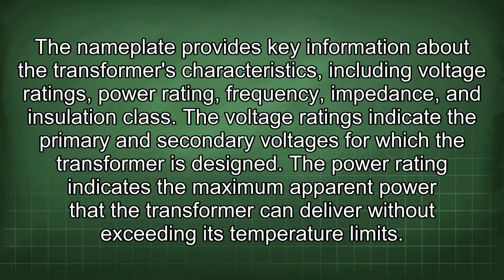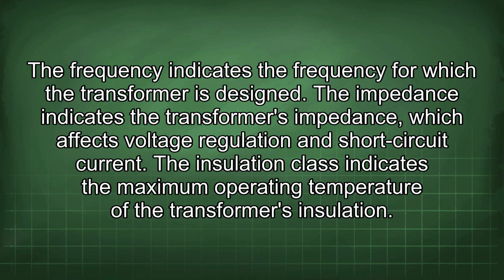The power rating indicates the maximum apparent power that the transformer can deliver without exceeding its temperature limits. The frequency indicates the frequency for which the transformer is designed. The impedance indicates the transformer's impedance, which affects voltage regulation and short-circuit current. The insulation class indicates the maximum operating temperature of the transformer's insulation.